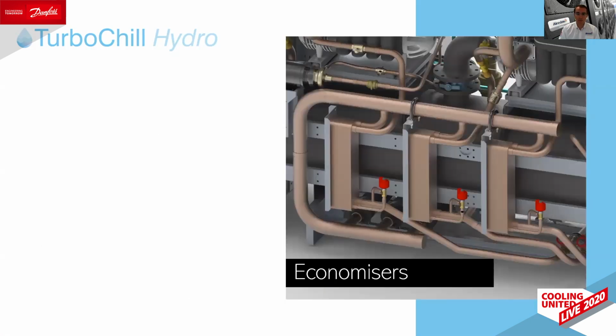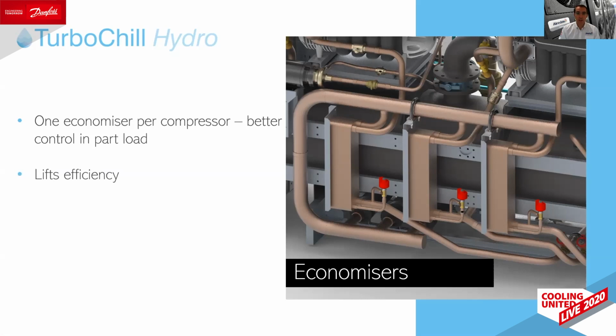We have an economised electronic expansion valve per compressor, controlled intelligently by the Helix controls platform to give greater performance and efficiency in part load conditions. Typically, chillers have an economiser per compressor, which are in use all of the time, irrespective of the numbers of compressors active, compromising part load efficiencies. The TurboChill Hydro is different and only allows refrigerant mass flow through the economiser that the compressor is coupled with. During part load operation, this yields the benefits of increased efficiency and additional cooling capacity through full use of the economiser plate. Testing has shown that Airedale's innovative approach has yielded an additional 5% of cooling capacity.